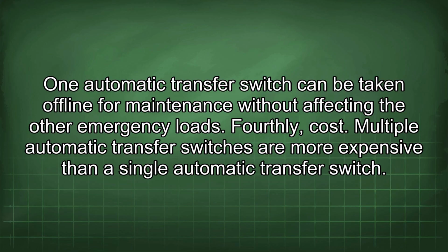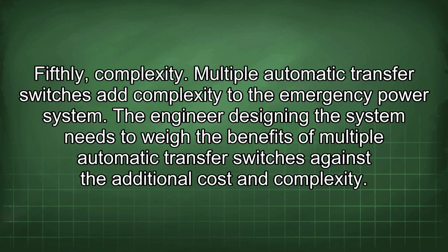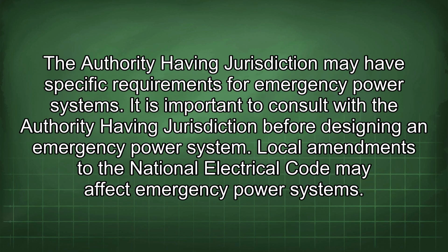Fourthly, cost. Multiple automatic transfer switches are more expensive than a single automatic transfer switch. Fifthly, complexity. Multiple automatic transfer switches add complexity to the emergency power system. The engineer designing the system needs to weigh the benefits of multiple automatic transfer switches against the additional cost and complexity. The authority having jurisdiction may have specific requirements for emergency power systems.